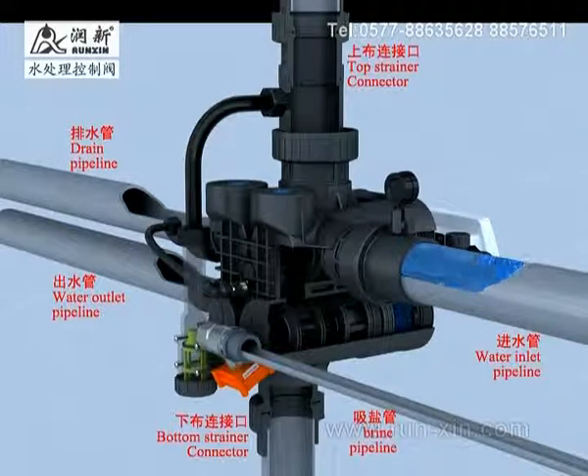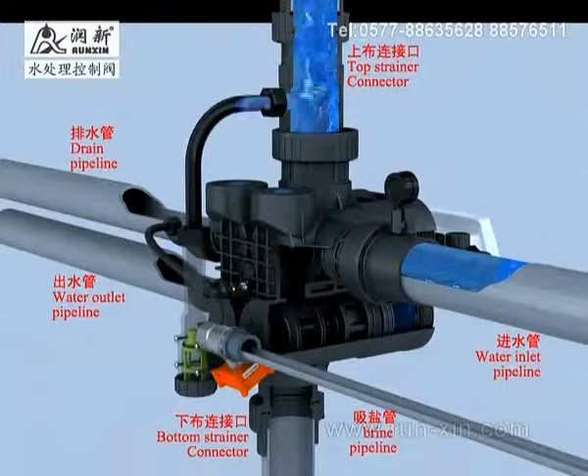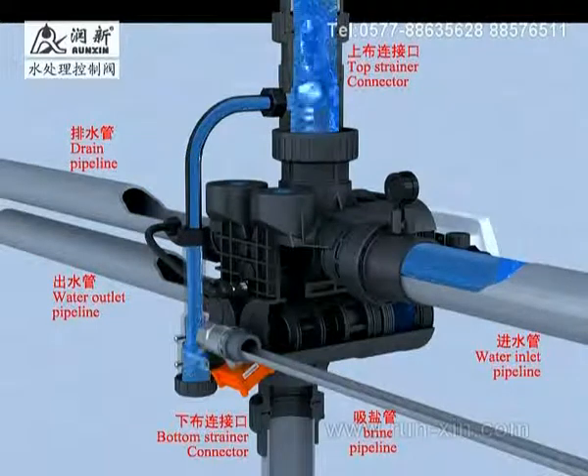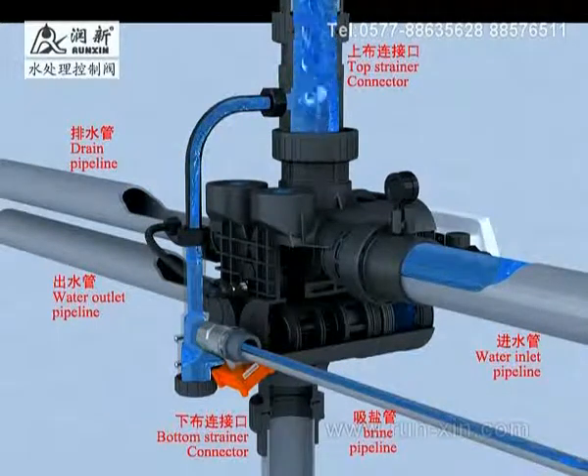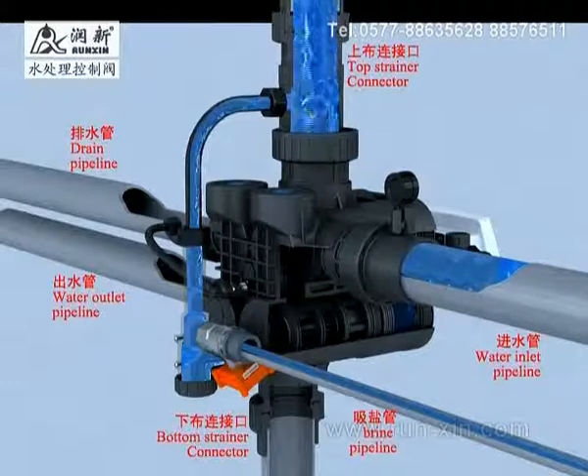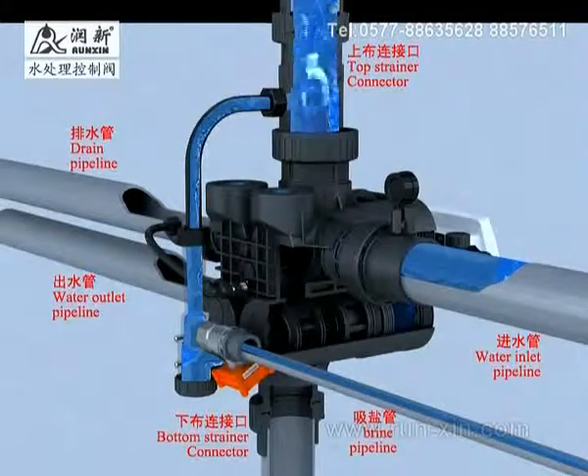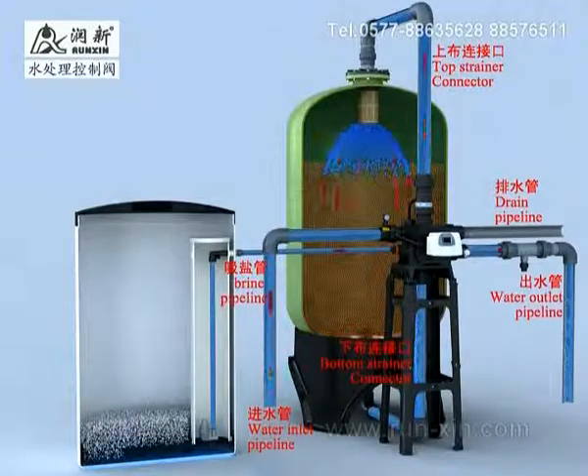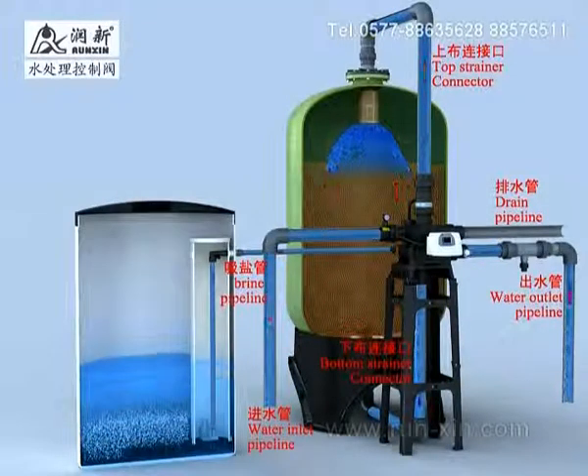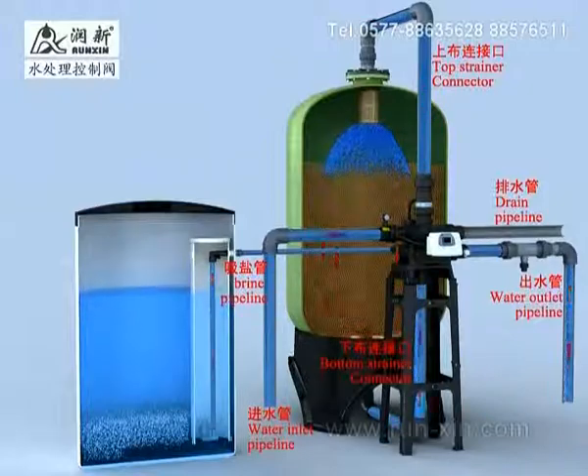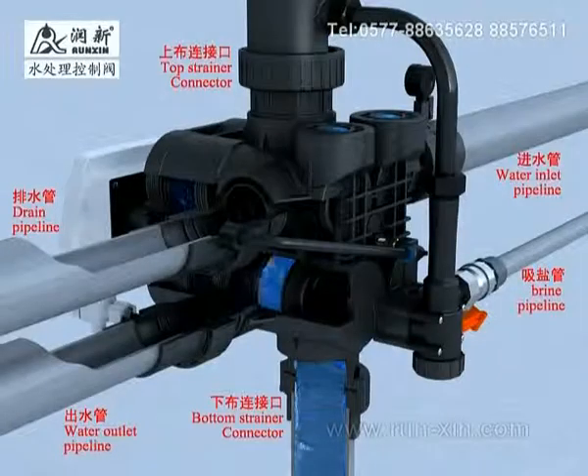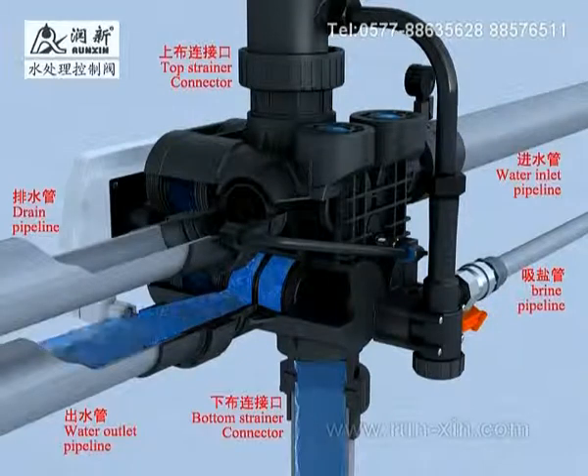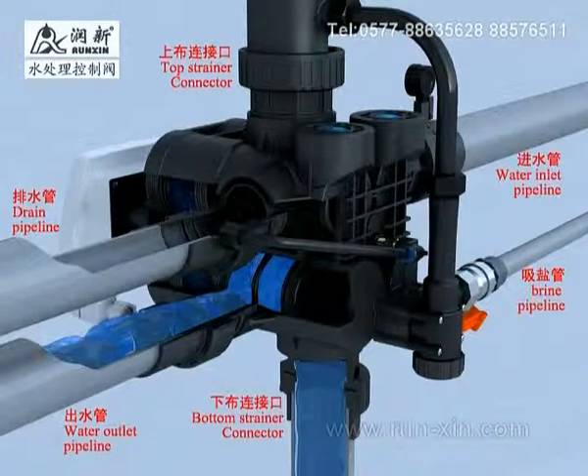Most parts of raw water through the water inlet go into 3 parts valve A, through the top of the main valve and top strainer and into the tank. Small parts of raw water through the injector fill into the brine tank by the electronic brine valve. At the same time, the electronic brine valve should be opened. Then water goes down through rising layers to become softened water, through the bottom strainer, returns to 3 parts valve C, and flows out from the water outlet. When it arrives at the set time, brine refill is over, then it enters into service state.